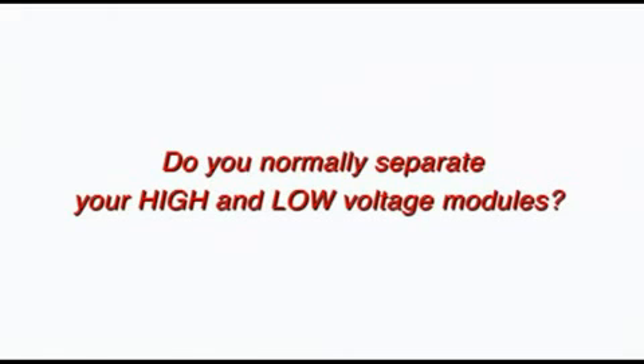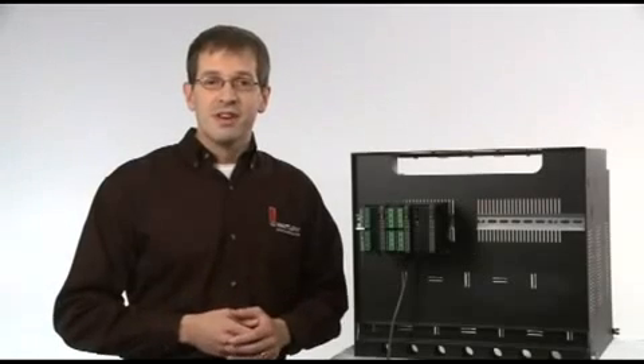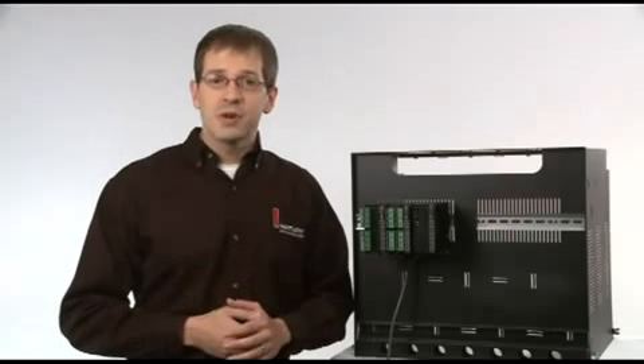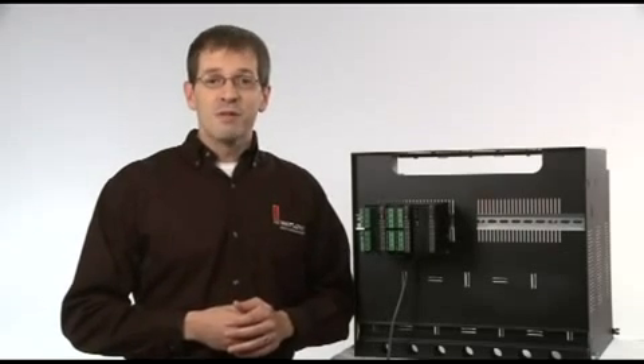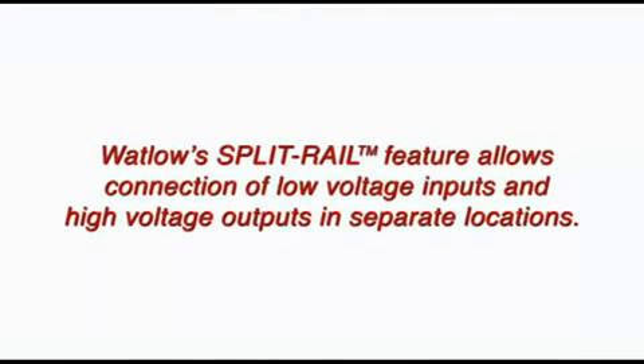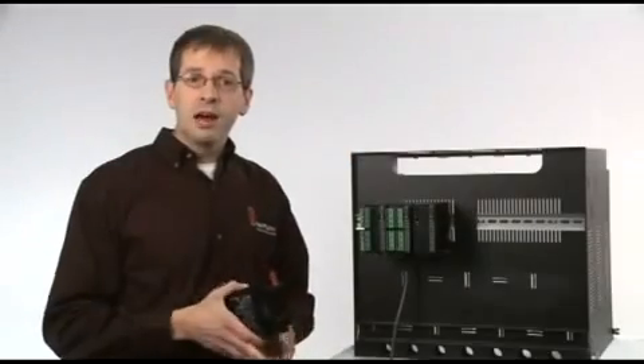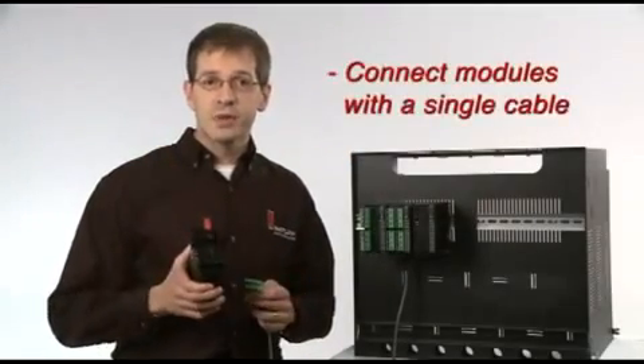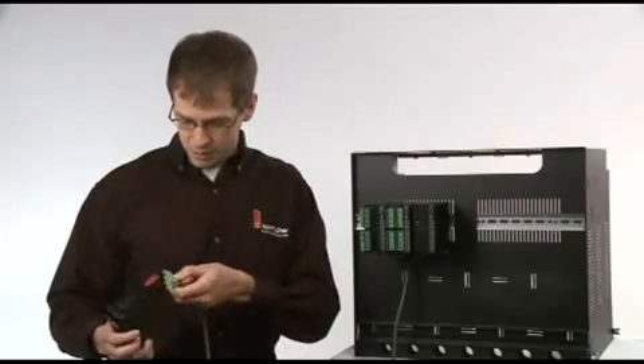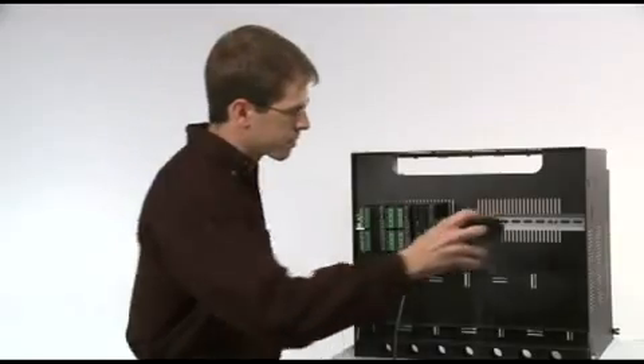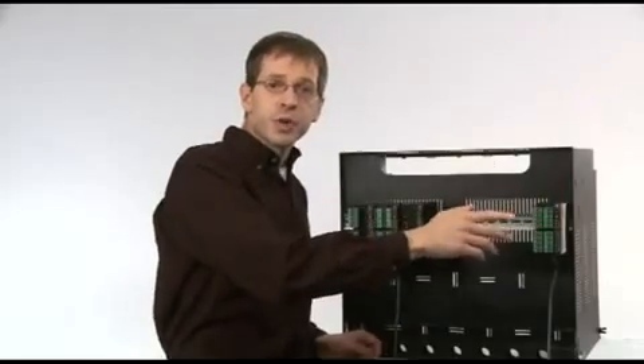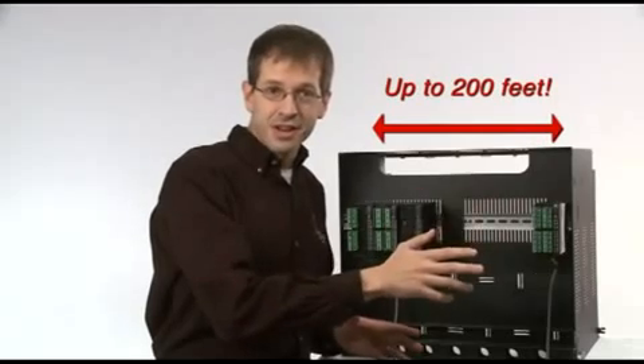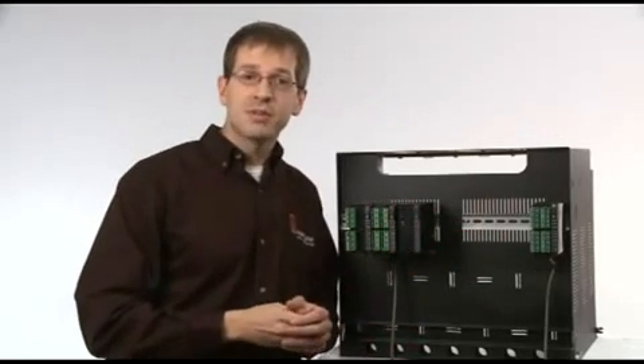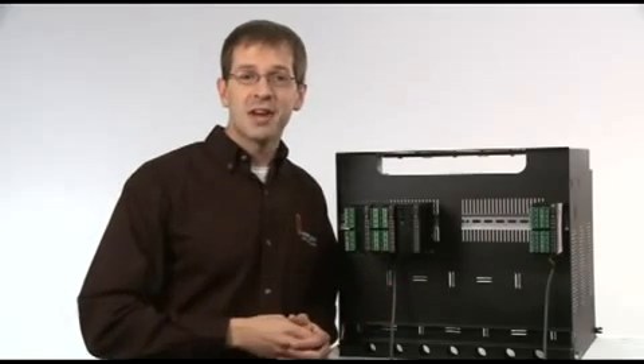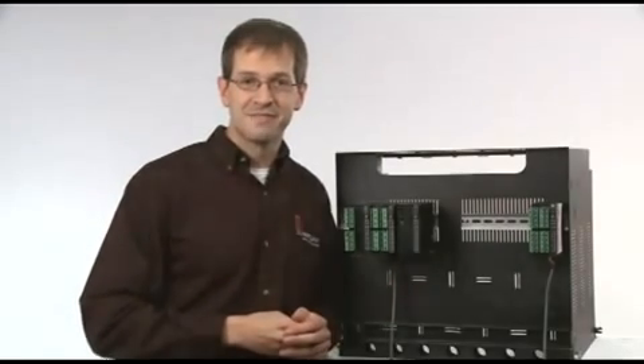Do you normally separate your high and low voltage modules for safety or agency purposes? Are you frustrated with having to make lengthy and expensive sensor and input-output cable runs? Well, we've simplified that process by incorporating a split rail feature in the EZ-ZONE RM. You can locate low voltage inputs in one area and high voltage outputs in another, and then connect the 2 sets of modules with one simple cable. The distance between the split modules can be up to 200 feet. This splitting can occur multiple times, allowing modules in the same system to be installed in several locations, minimizing the effort to install and wire input and output devices.